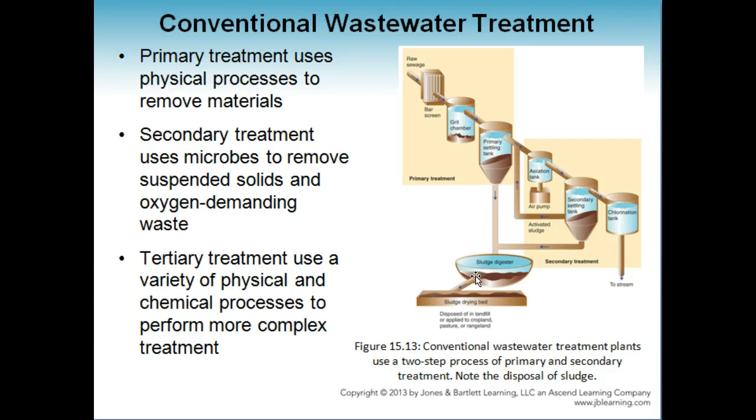Secondary treatment is designed to substantially degrade the biological content of the sewage, which is derived from human waste, food waste, soaps, and detergents. The majority of municipal plants treat the settled sewage liquor using aerobic biological processes. To be effective, the bacteria, or activated sludge, require both oxygen and food to live. The bacteria and the protozoa in the sludge consume biodegradable, soluble organic contaminants like sugars, fats, short-chain carbon molecules, etc., and bind much less of the soluble fractions into the floc.